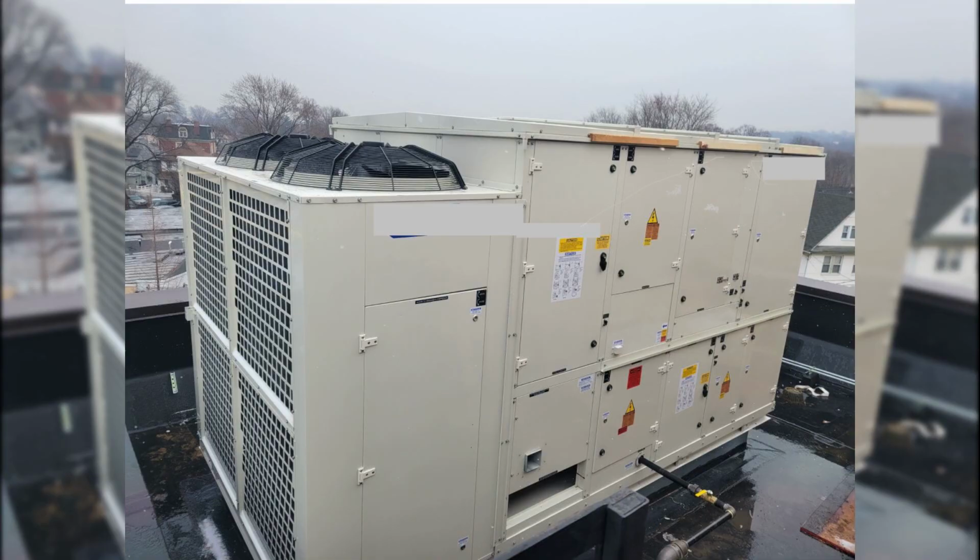Key design requirements and components. 5. Air discharge and fans. Both DX and dual-temperature air handling units must have a nominal air discharge of 55 degrees Fahrenheit in cooling mode and be equipped with airfoil plenum or fan array supply and exhaust fans. 6. Filtration. DX heat pump units and dual-temperature air handling units must have pre-filters with a minimum MERV 8 rating and final filters with a minimum MERV 13 rating.